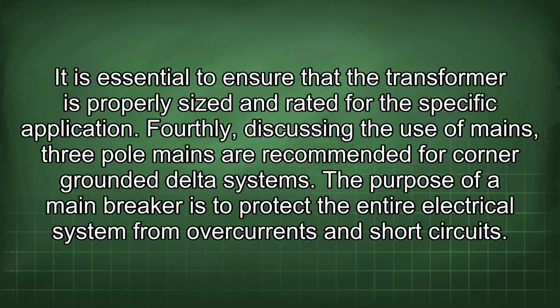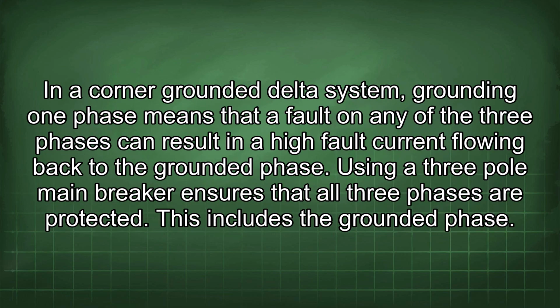Fourthly, discussing the use of mains, 3-pole mains are recommended for corner-grounded delta systems. The purpose of a main breaker is to protect the entire electrical system from overcurrents and short circuits. In a corner-grounded delta system, grounding one phase means that a fault on any of the three phases can result in a high fault current flowing back to the grounded phase.